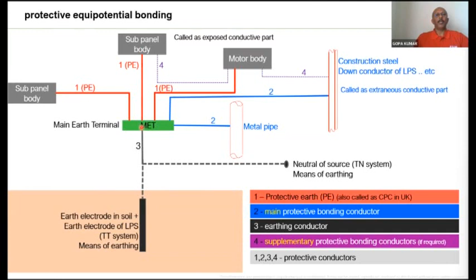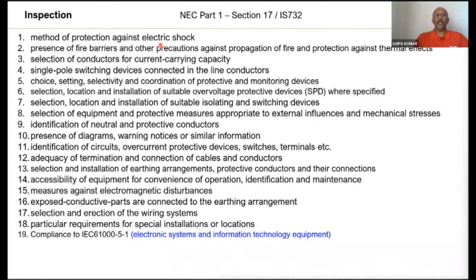IS 732 of 1989, 32 years back, included inspection and testing in the standard. There are 18 points to be inspected, starting from the method of protection against electric shock, meaning how the designer has designed the electrical system to handle shock, handle fire, and so on. Similarly, there are 10 different subjects for testing. Resistance of conductors means if you do this particular test, all the loose contacts can be found out.